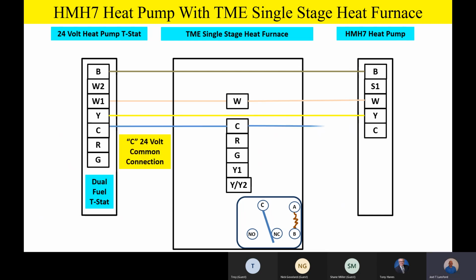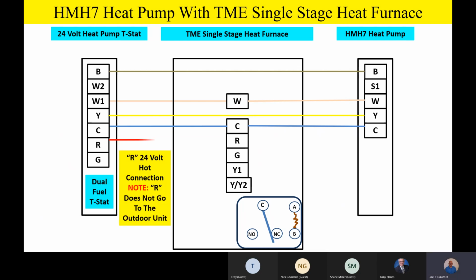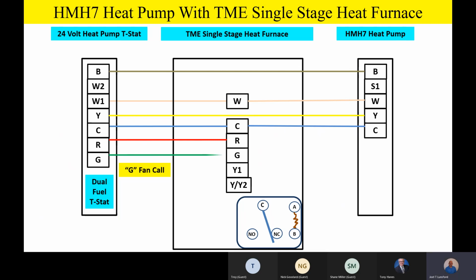C is our 24-volt common, just like we had before. This is probably looking real familiar to you because it's the same type of wiring, except we're doing it on a furnace now instead of an air handler. R is 24-volt hot. It does not go outside. G is our fan call, just like we had before.